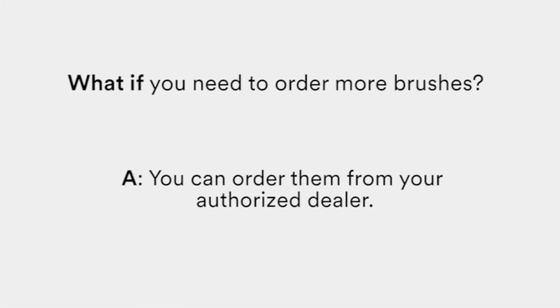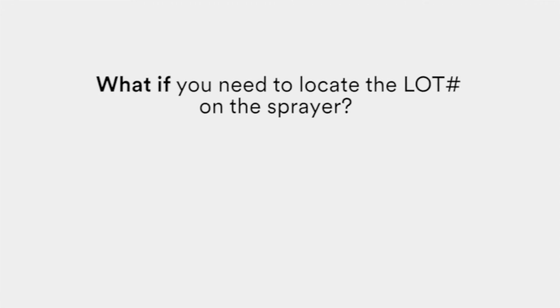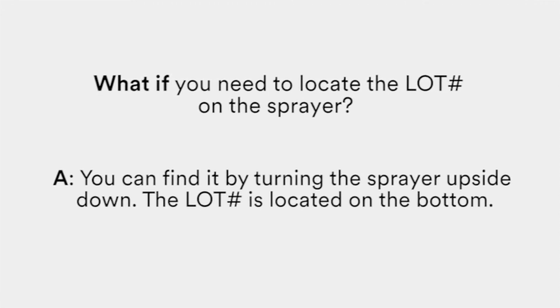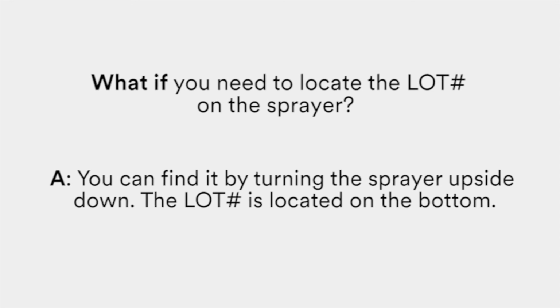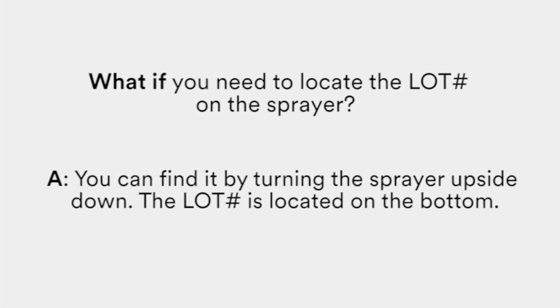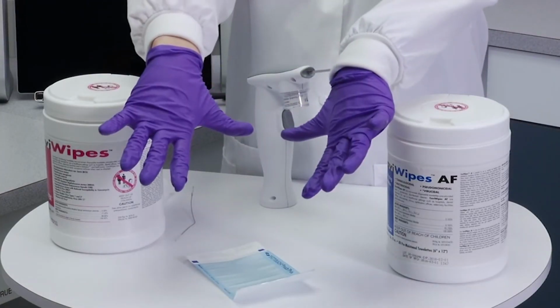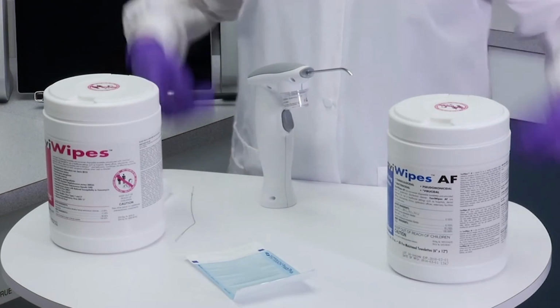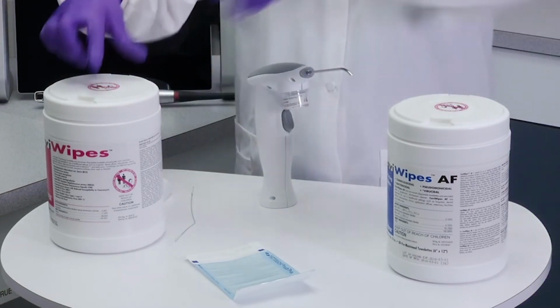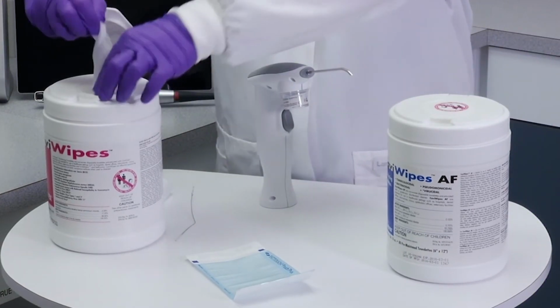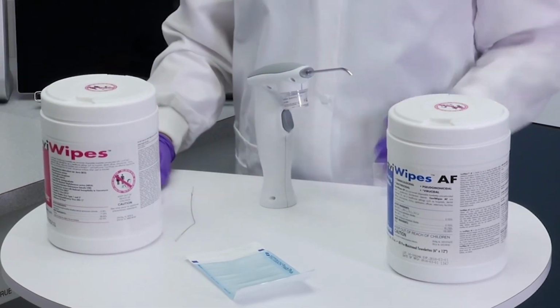You can order them through your authorized dealer. What if you need to locate the lot number on the sprayer? You can find it by turning the sprayer upside down. The lot number should be located on the bottom of the sprayer. Now that you know how to care for and maintain your sprayer, let's discuss the cleaning and disinfection procedure for the sprayer. For the cleaning procedure of the sprayer, put on a pair of fresh gloves. Wipe down all surfaces with an intermediate level disinfectant, such as CaviWipes AF, CaviWipes, or the equivalent.